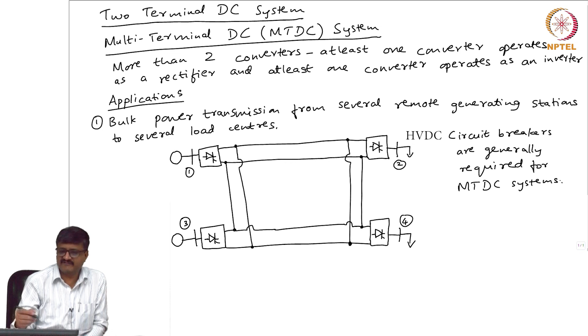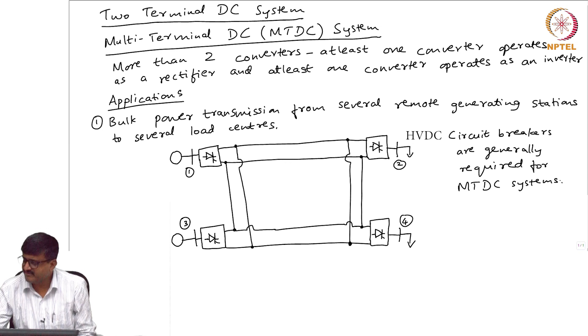The point is you have control over the thyristors. So you can always control the thyristors and completely block the current. But if you do that here, you are not isolating only the faulty component, you are affecting the other parts of the system. So when you have an MTDC system, a breaker is a must. Breakers are generally required for MTDC systems, but it's okay to not have a breaker for a 2-terminal DC system. So this is one application.